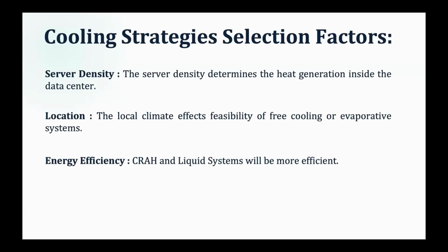Now, based on what factors do we select a cooling strategy? Of course, one is server density. If all the server racks are populated with many servers within a very small confined space, the heat density will be more. With the heat density being more, the cooling capacity required will be more. So that depends on whether we go for hybrid cooling, air cooling, or liquid cooling.